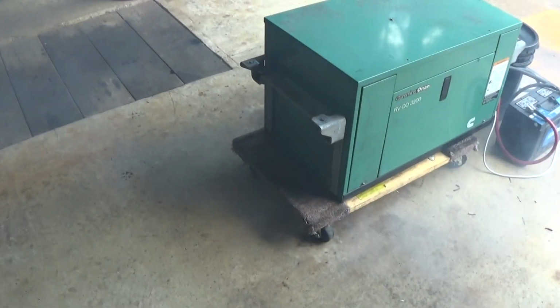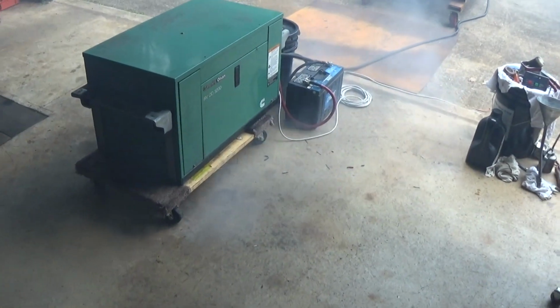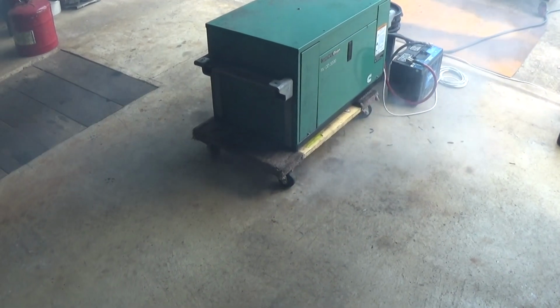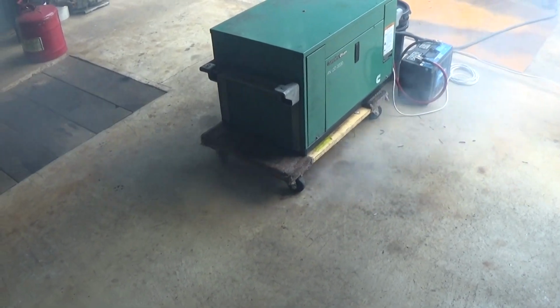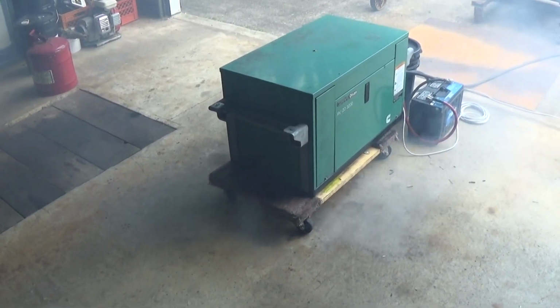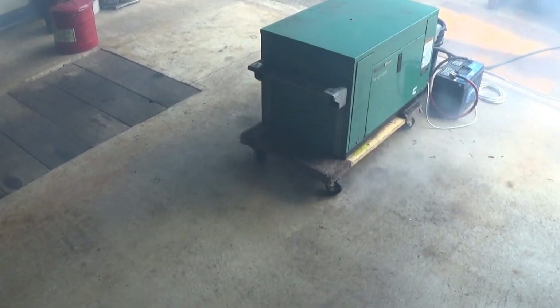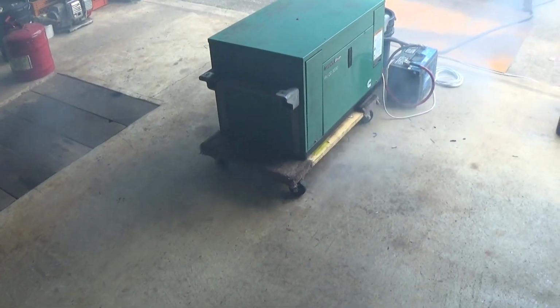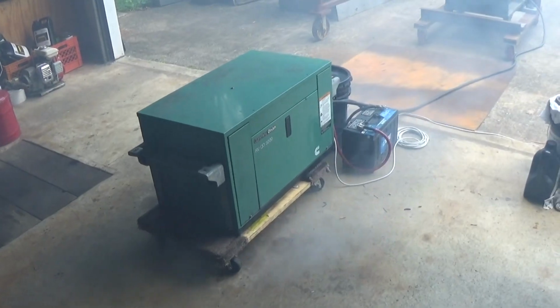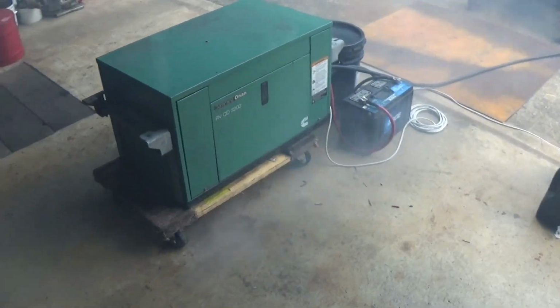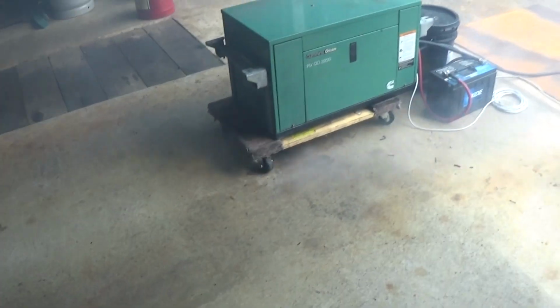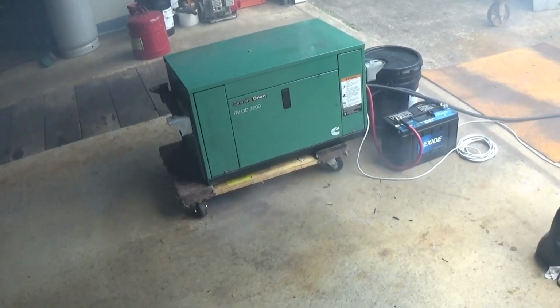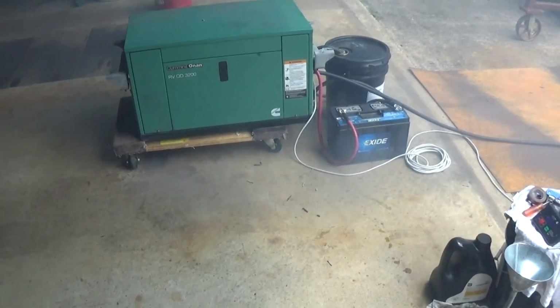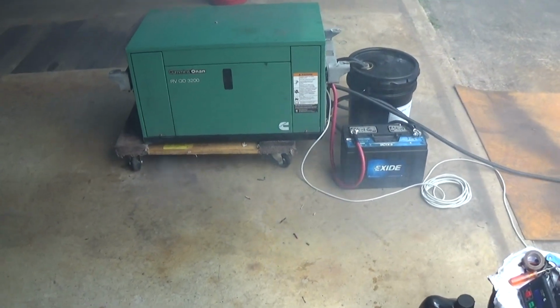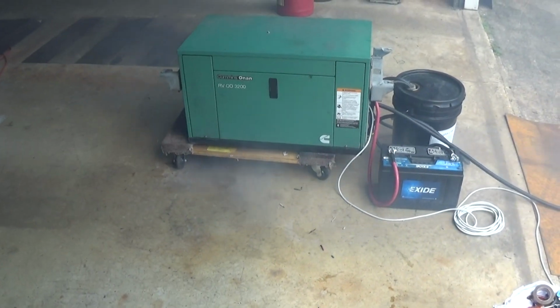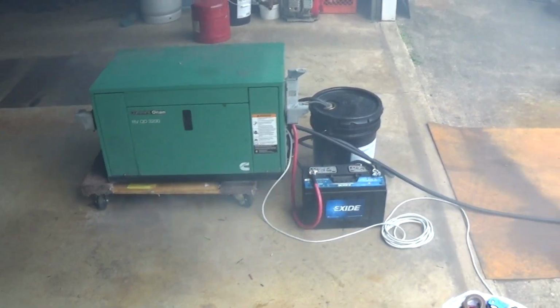The manual touches on wet stacking very briefly. It states the minimum load this unit should be operated on is 15%. And even at that, if it's operated at a low load like that for an extended period of time, the load should be ramped up to almost 100% for a few minutes before the unit is shut down.